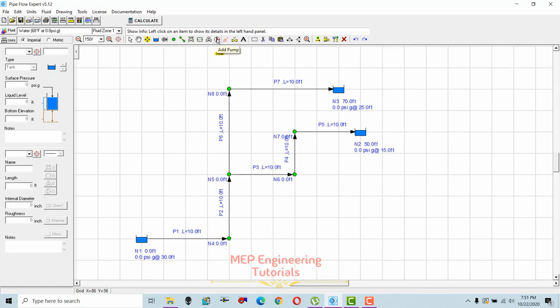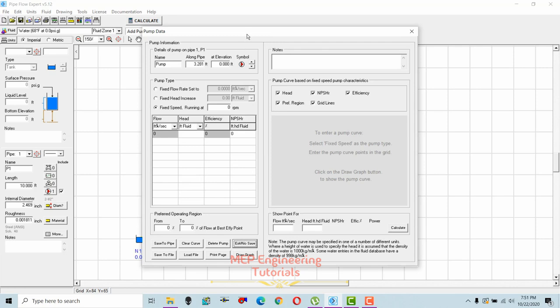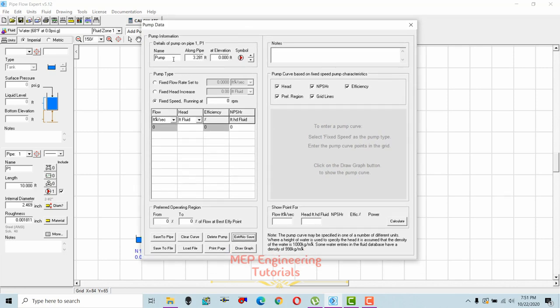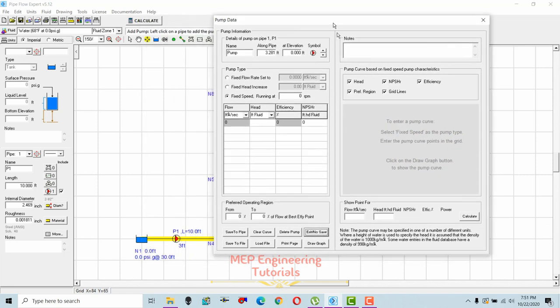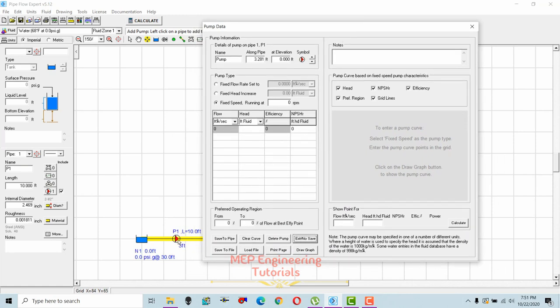To add a pump, select it from the toolbar and click on the pipe where you want to place it. If you want to change default data, select yes to open the pump dialog box. There are three pump types: fixed flow rate, fixed head increase, or fixed speed. Since the total demand is 200 gpm, I'll use the fixed flow rate option set to 200 gpm.